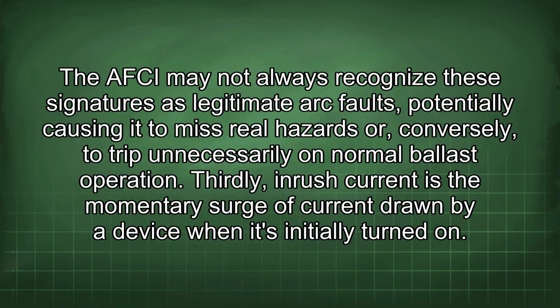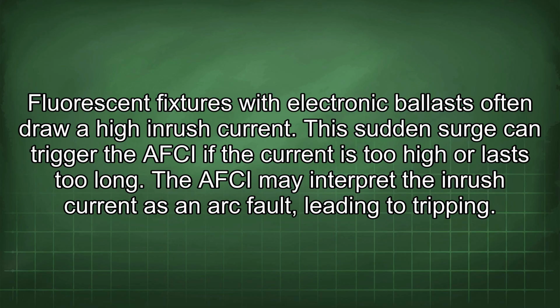Thirdly, inrush current is the momentary surge of current drawn by a device when it's initially turned on. Fluorescent fixtures with electronic ballasts often draw a high inrush current. This sudden surge can trigger the AFCI if the current is too high or lasts too long. The AFCI may interpret the inrush current as an arc fault, leading to tripping.